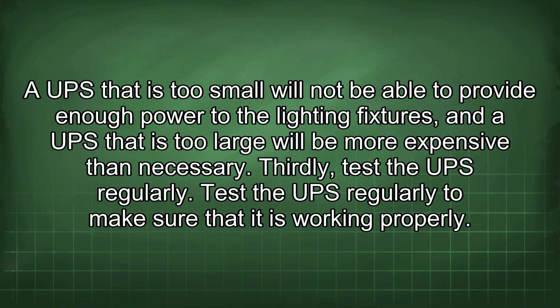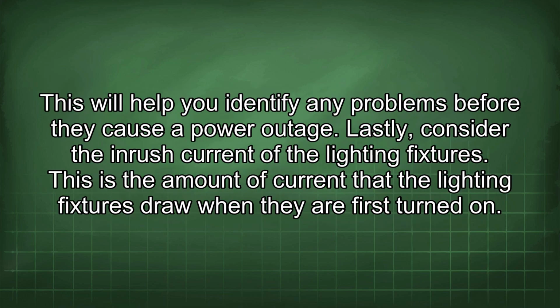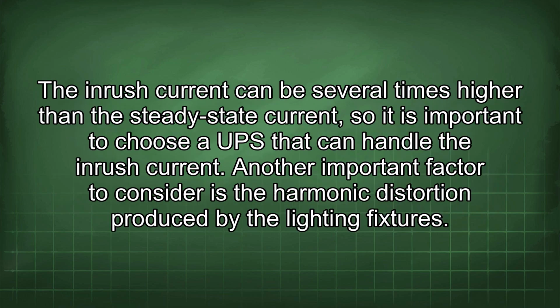Thirdly, test the UPS regularly. Test the UPS regularly to make sure that it is working properly. This will help you identify any problems before they cause a power outage. Lastly, consider the inrush current of the lighting fixtures. This is the amount of current that the lighting fixtures draw when they are first turned on. The inrush current can be several times higher than the steady-state current, so it is important to choose a UPS that can handle the inrush current.